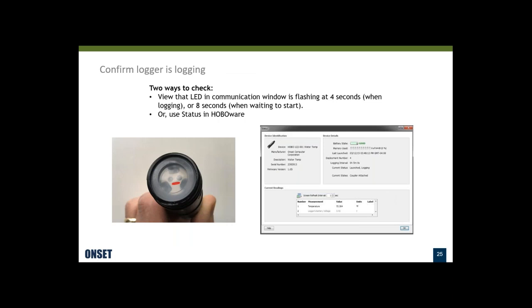As I'm deploying the loggers, I want to make sure they really are logging. There's a little LED that flashes every four seconds when the logger is logging, or every eight seconds if it's waiting to start. You look in the end of the logger — it looks like a little face — and that little red smile flashes every four seconds or so.